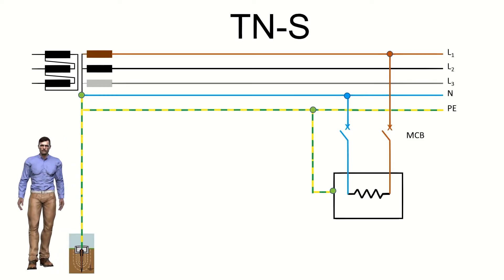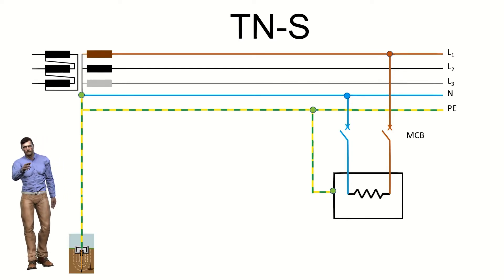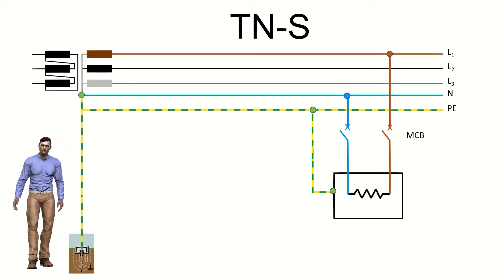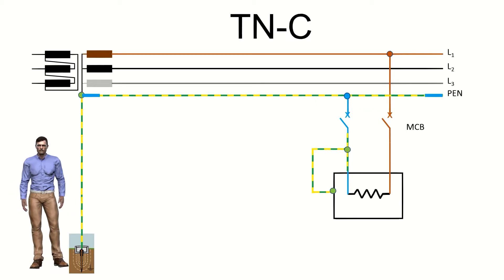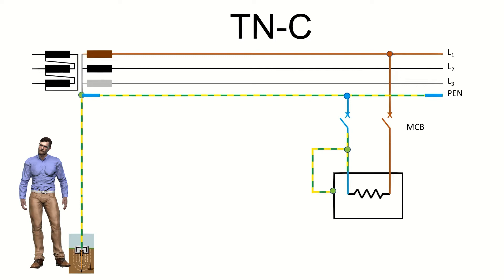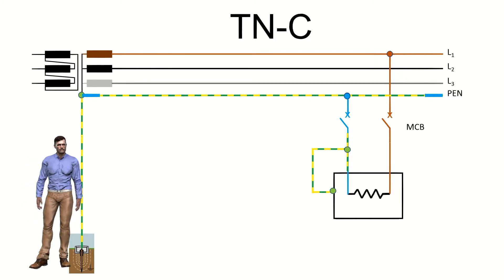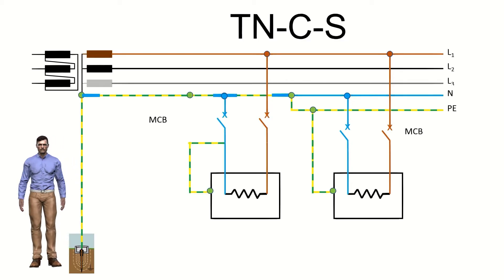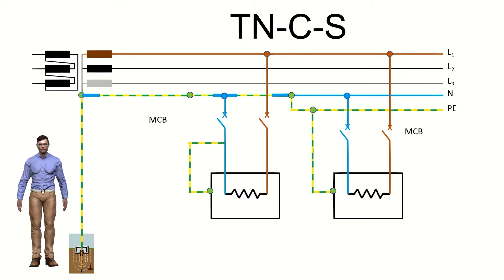In the TNS diagram, we see the neutral of the supply grounded, and from that point two conductors come out that reach the receiving installation: one that acts as a neutral, called N, and the other that acts as a protective conductor, called PE. In the TNC diagram, the neutral is also grounded, but from this point only one conductor is delivered that reaches the receiving installation and acts as both a neutral and a protective conductor, denominated by the letters PEN. In the TNCS scheme, a single PEN conductor will arrive in some part of the installation, and in others it will be divided into two conductors: one for neutral and the other for protection.